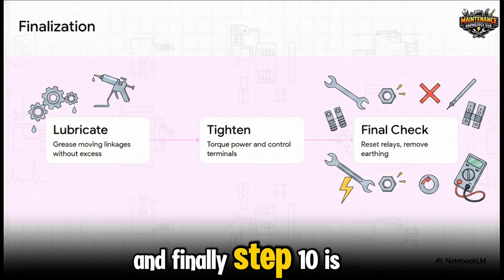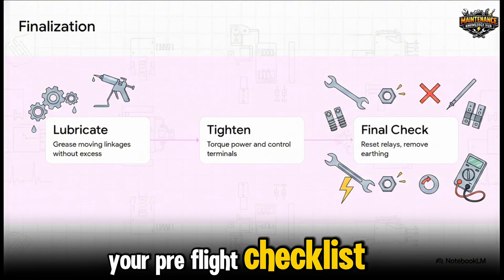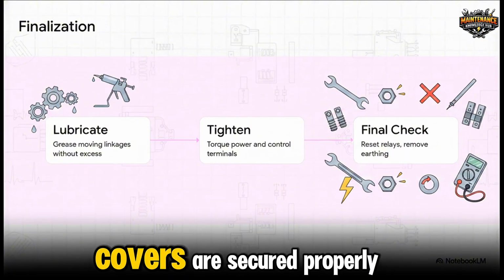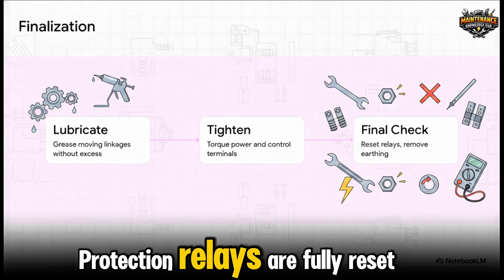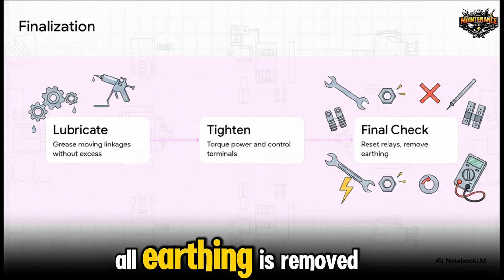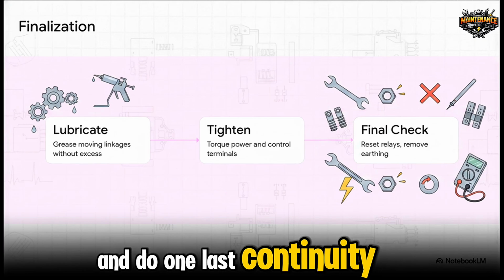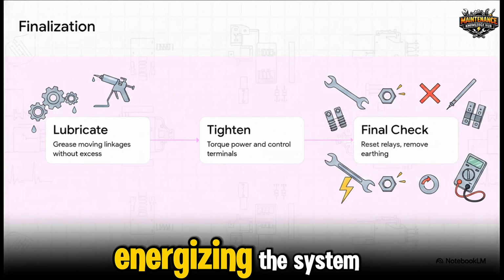And finally, step 10 is your pre-flight checklist. Make sure the unit is spotless, covers are secured properly, protection relays are fully reset, all earthing is removed, and do one last continuity check before you ever think about energizing the system.